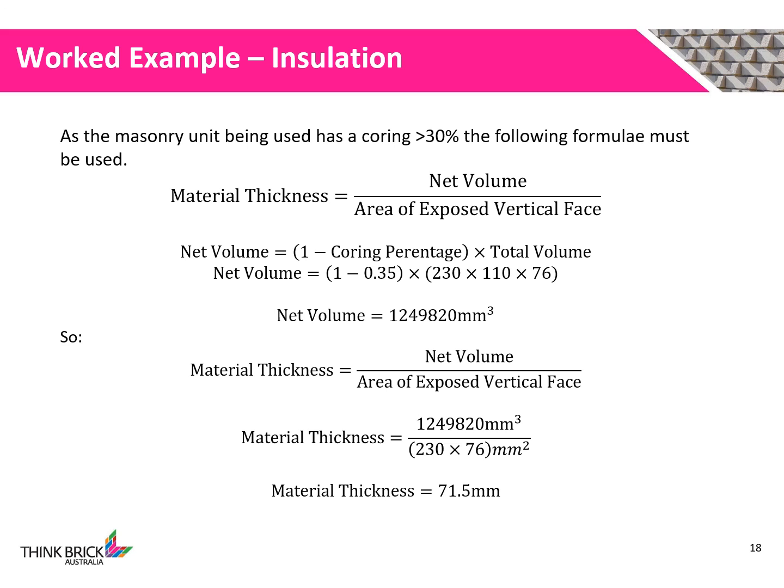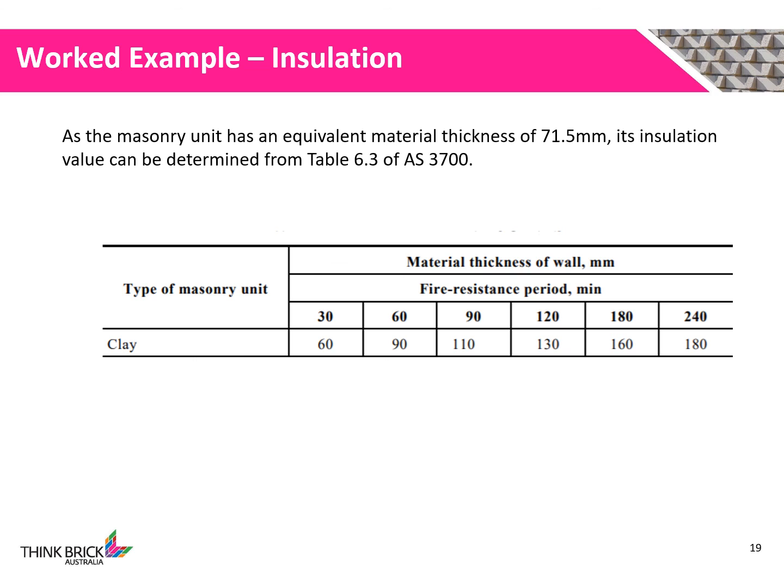As our masonry unit has voids greater than 30%, we must use the material thickness formula: material thickness equals net volume divided by the area of the exposed vertical face. Net volume is equal to the total volume of the unit times one minus the coring percentage. The area of the exposed vertical face is simply the area of the brick face: 230mm by 76mm. Substituting these numbers in, we determine the material thickness to be 71.5mm. Using Table 6.3 of AS 3700, we can determine the insulation value. As our material thickness does not meet or exceed 90mm, the 60mm threshold value must be adopted, giving an insulation value of 30 minutes.